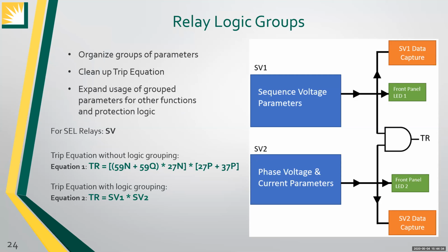For our detection logic, the trip equation, denoted by TR, would be written as shown here by equation 1. If we group the sequence voltage parameters, the terms in the first set of brackets, and the phase voltage and current parameters in the second set of brackets as SV1 and SV2 respectively, then our trip equation is much shorter and simpler, as shown in equation 2. This allows these group parameters to be used for other functions in addition to circuit breaker tripping, without needing to re-enter the parameters individually each time. Instead, we can simply enter SV1 into an alarm setting or assign it to a front panel LED instead of entering these 3 terms every time.